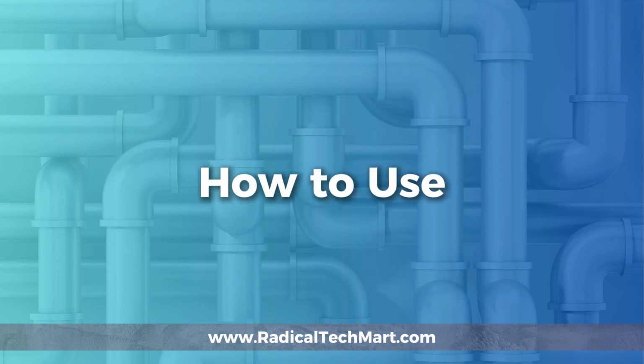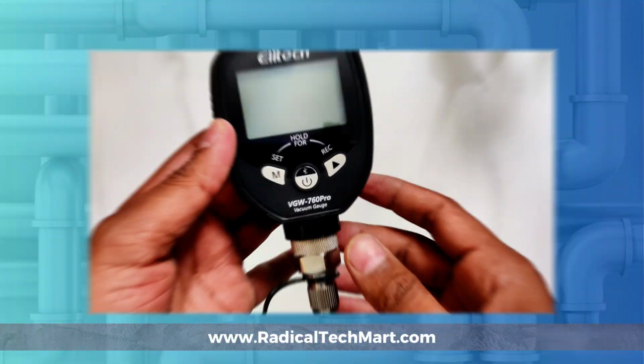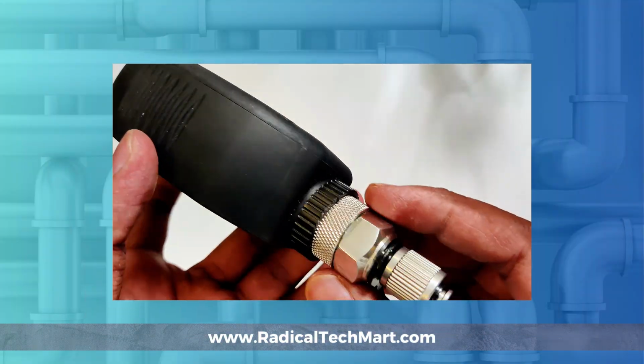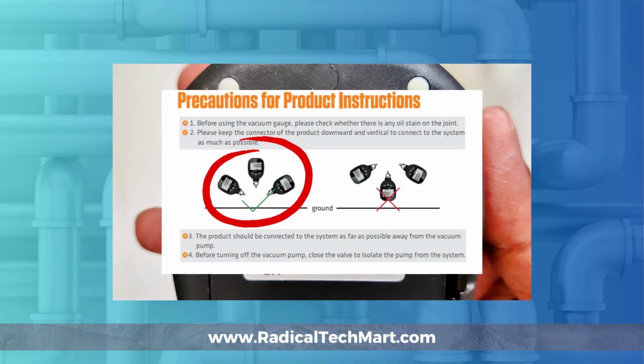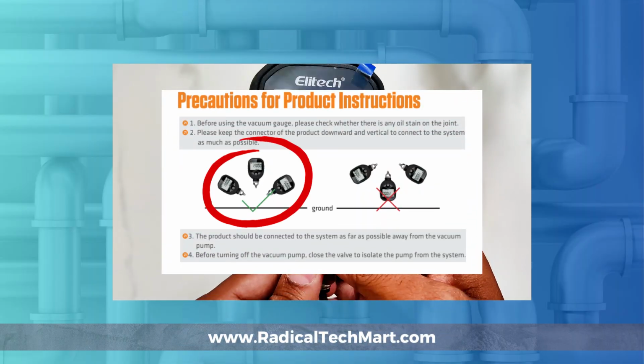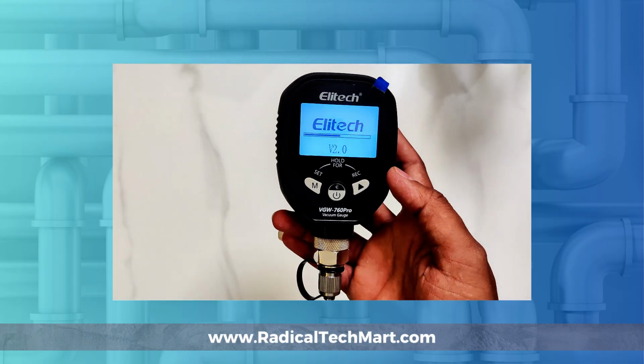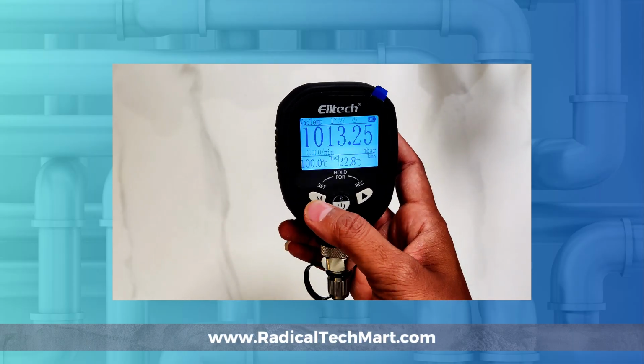Before using the gauge, first check the joint. Make sure there is no oil stain or dirt. Connect the gauge properly to the system. The manual suggests keeping the connector downward and vertical as much as possible. Also, connect the gauge away from the vacuum pump as far as possible.